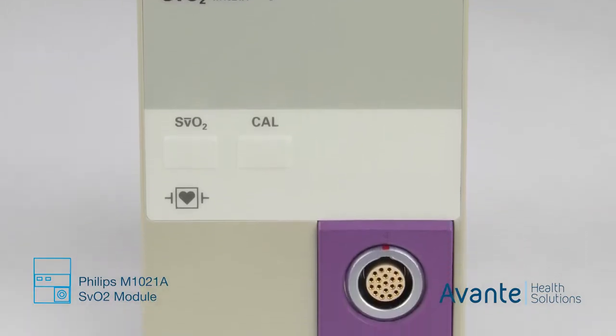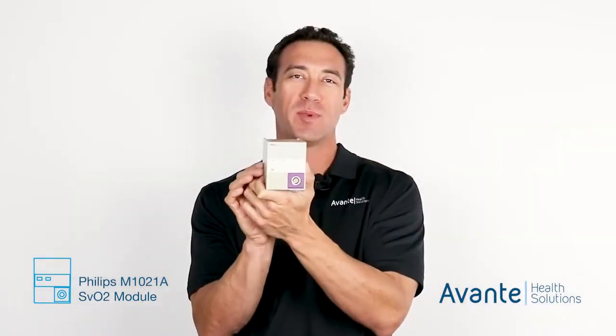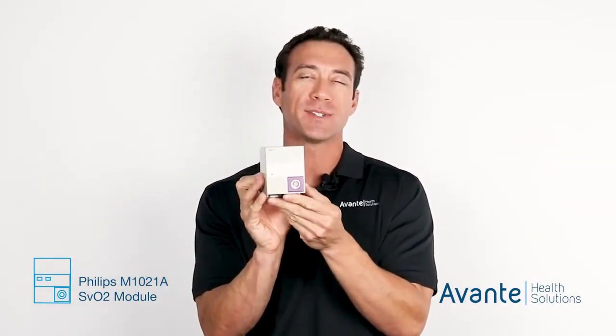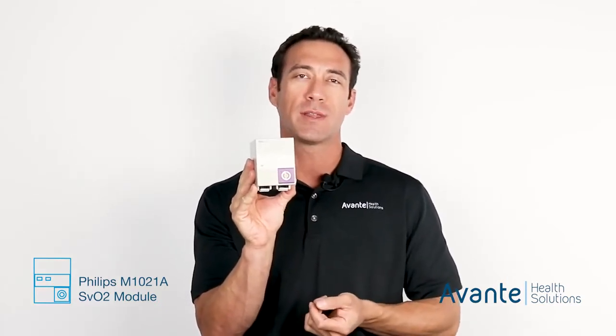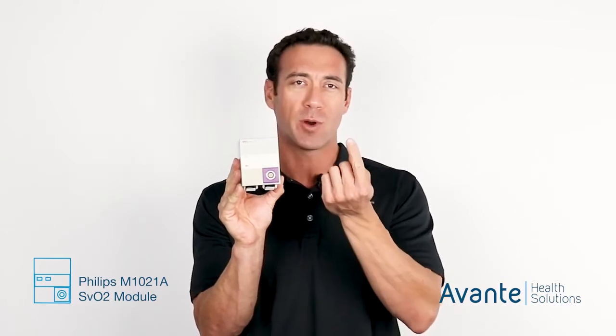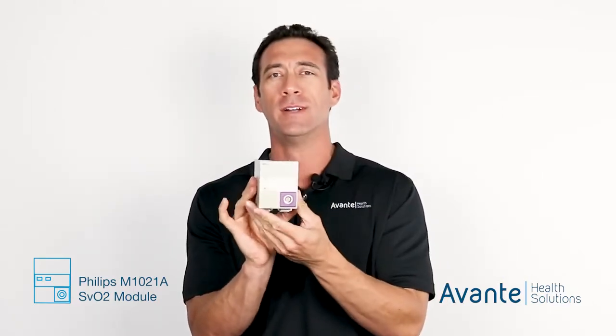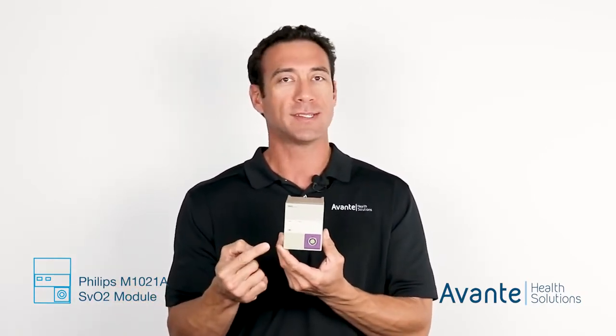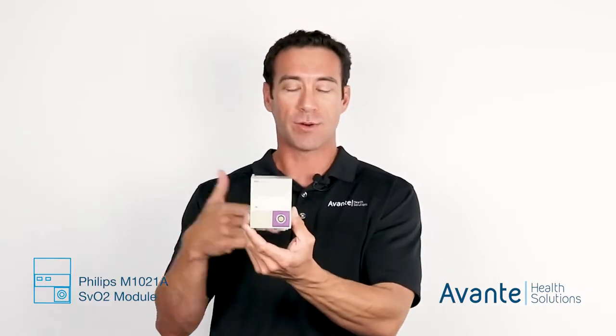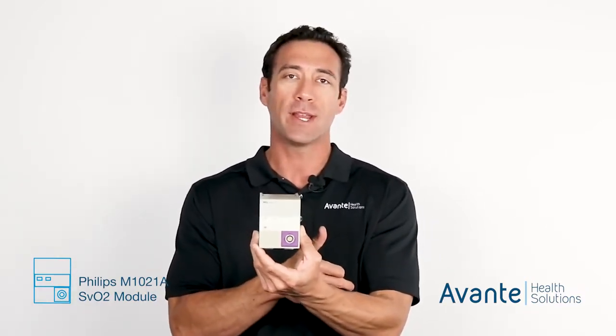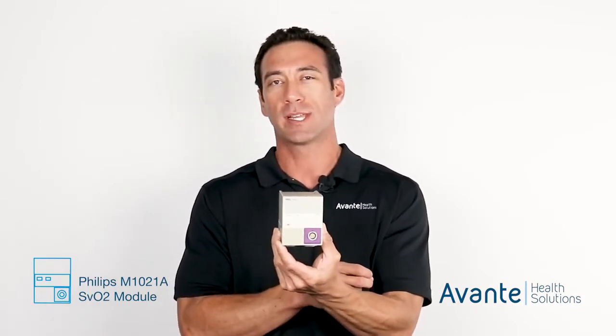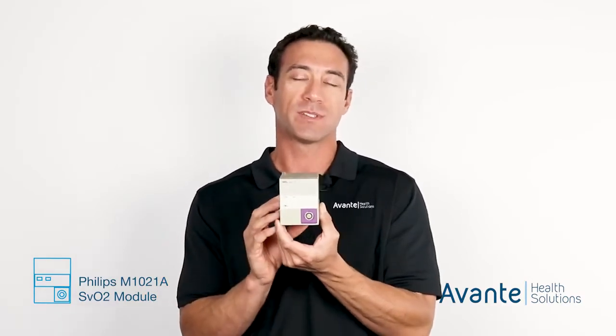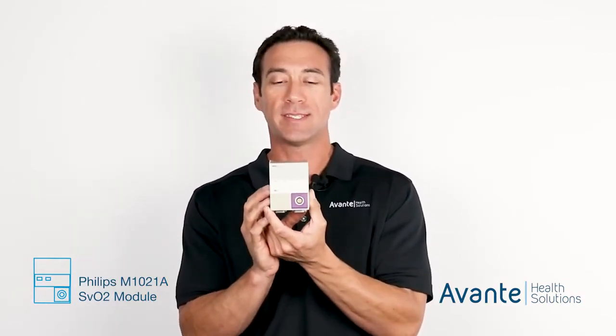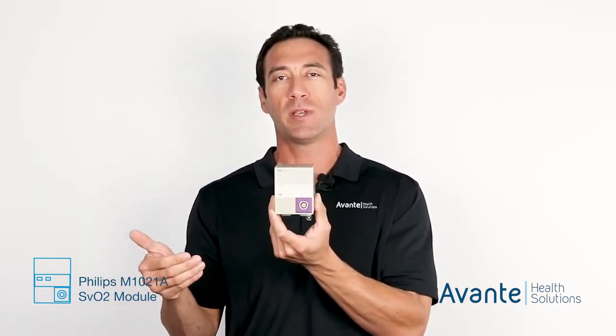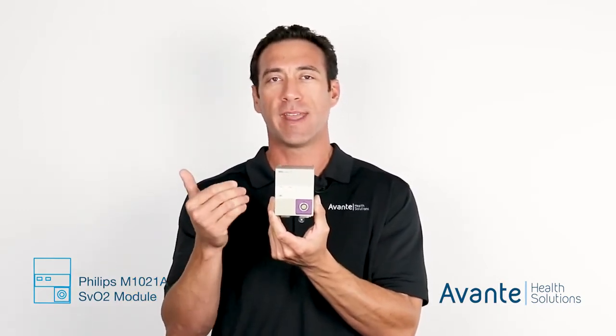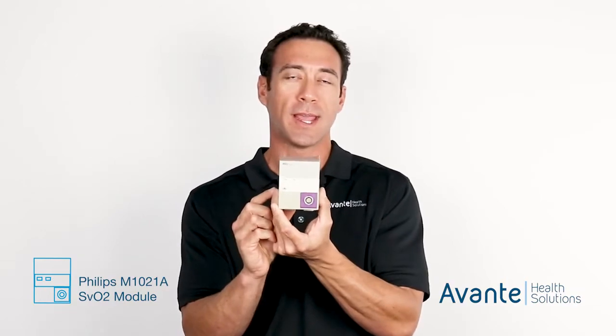So now I'm holding the Philips M1021A module. This is going to be your SvO2, and that's going to stand for your saturation venous oxygenation levels. So rather than your standard SpO2, which is going to be a non-invasive probe that's going to have the light shooting right into your finger to measure the oxygenation levels of your blood, this one is actually going to have an electrode that's going to go directly via cannula into your vein or artery. And inside of that, we'll have the light, which is going to gather direct information about the levels of oxygenation within your blood. So this would be more of an invasive measurement to measure that same measurement as an SpO2, but this is going to be the SvO2, so the venous oxygenation. And that's the Philips M1021A.